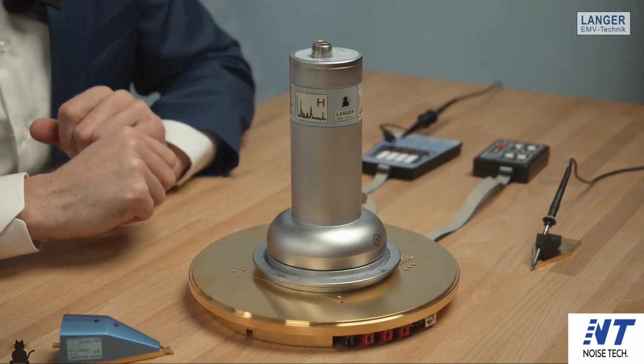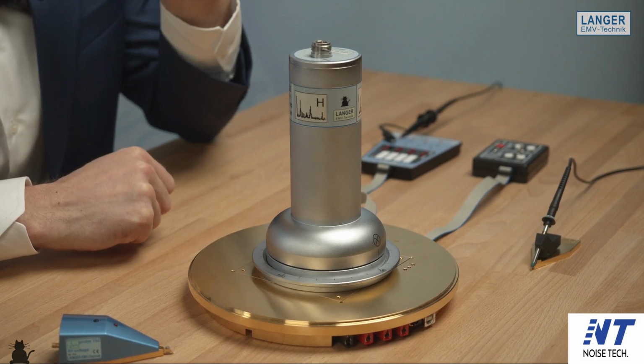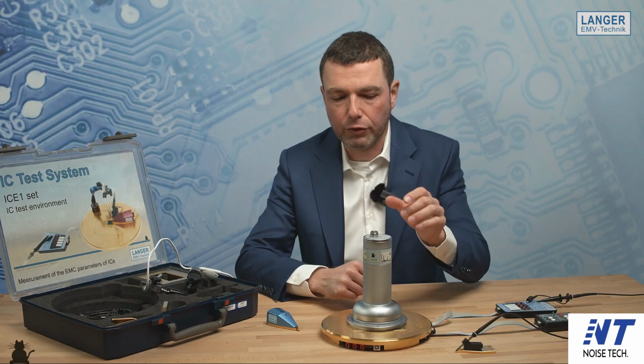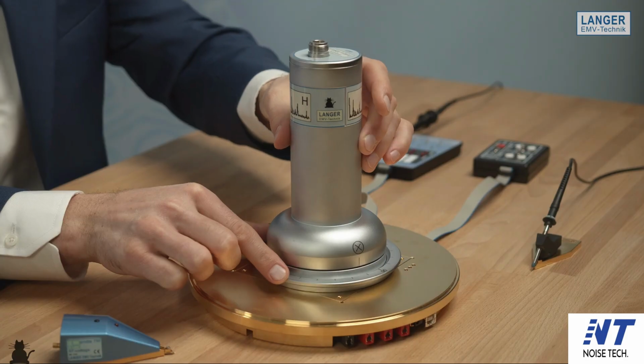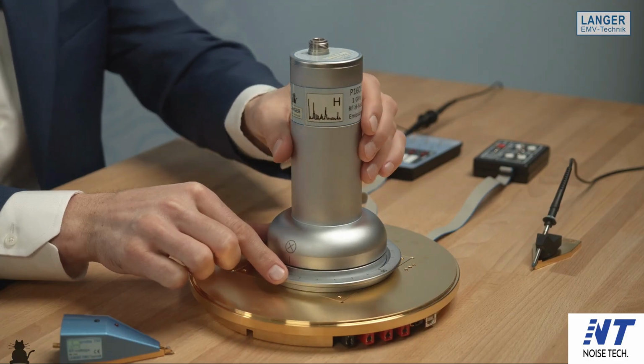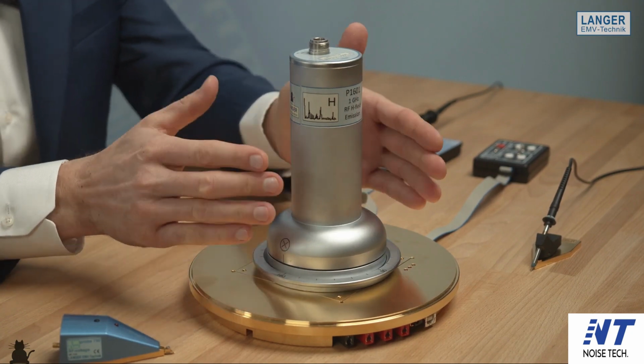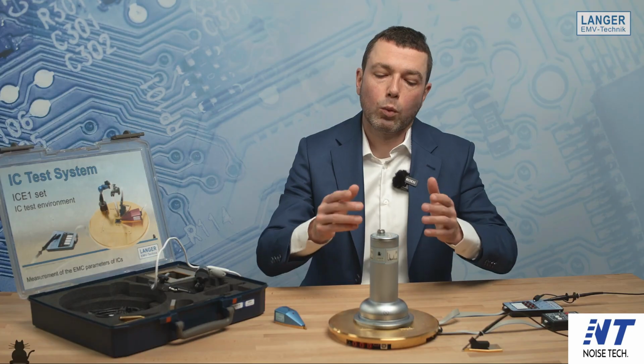On top of these probes here, you have the connections to the test equipment you need for such measurements. It is also possible now to rotate this probe, because with a magnetic field probe it is also important to measure in different directions. What I want to show you here is how easily you can change the test technology, whether you want to do emission or immunity testing, conducted or radiated. All measurements can be done with the same setup of the tested IC. An overview of the various test methods of the Langer IC test system you can see here in the table.